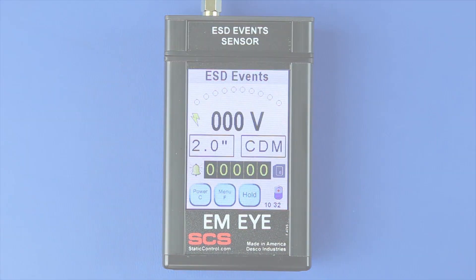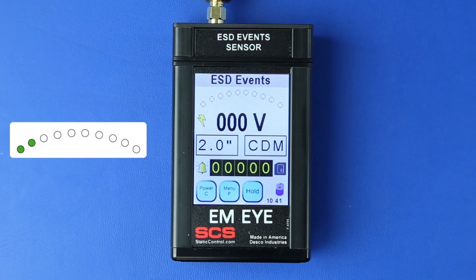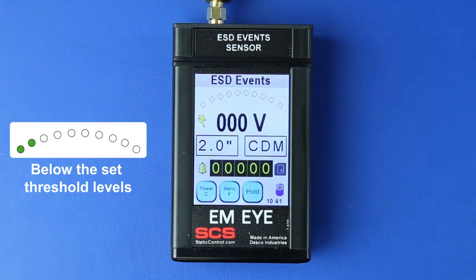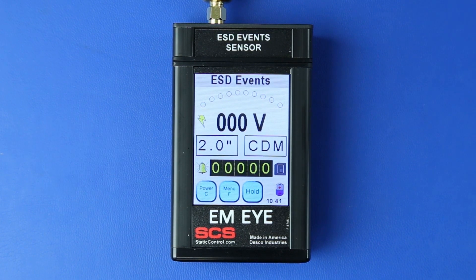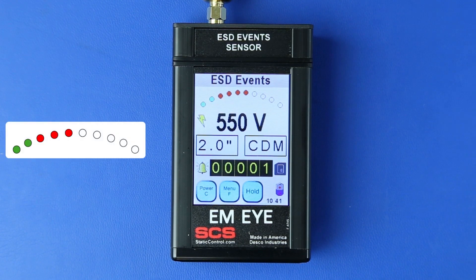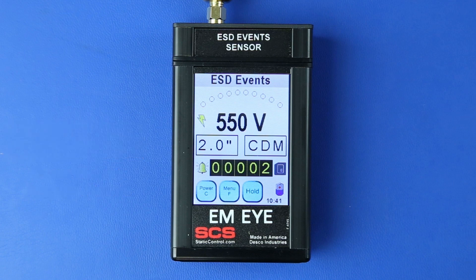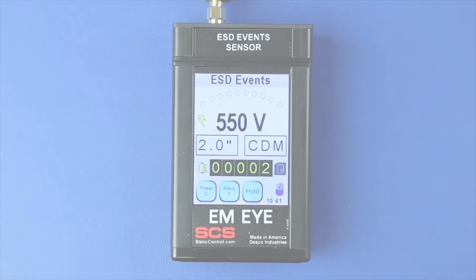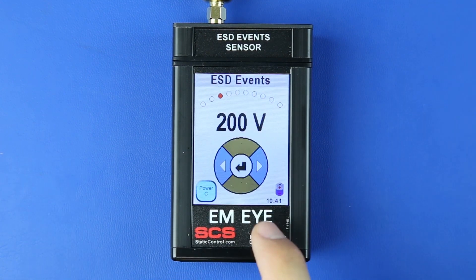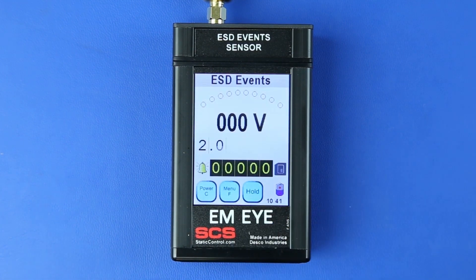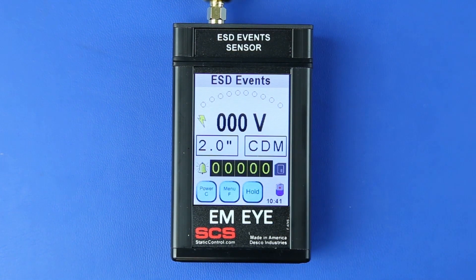Press the Enter button to save the settings and return to the home screen. The threshold arc displays the detection level of ESD events. Green indicates that the ESD event is below the set threshold — events below the threshold are not recorded. Red indicates that the ESD event is above the set threshold — events above the threshold are recorded. Press the threshold arc to open the ESD event threshold menu. Press the left or right arrows to set the desired ESD event voltage threshold, then press Enter to save and return to the home screen.